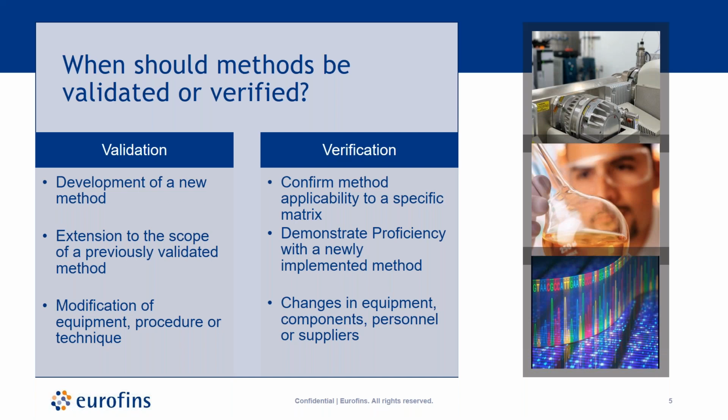So next, once again, we're going to be talking about this several times today, the difference between verification and validation, because it's very common to use the wrong terminology. It's important to remember that if you're implementing a previously validated method, then you'll either be transferring that method from the reference laboratory, or you'll verify under the actual conditions of use. That means implementing that procedure in your lab, on your equipment, with your personnel. So importantly, your lab will not revalidate the method, but you will be implementing a validated method.